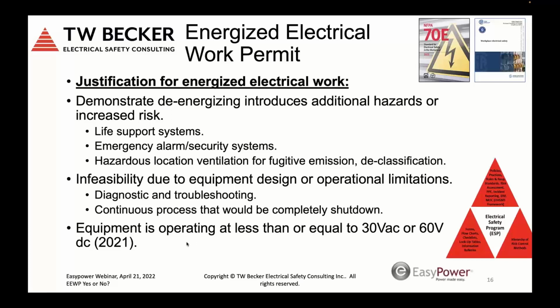You can perform energized work. There's no arc flash or shock hazard exposure risk to the qualified person. There's still an abnormal arcing fault, but that's not an arc flash. All right, so this is currently the listed justification for energized work.